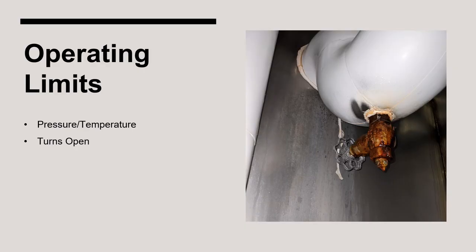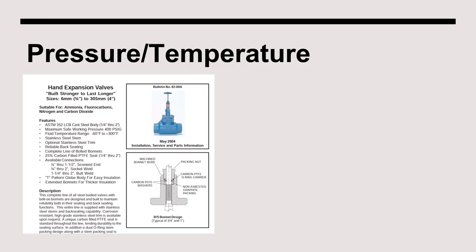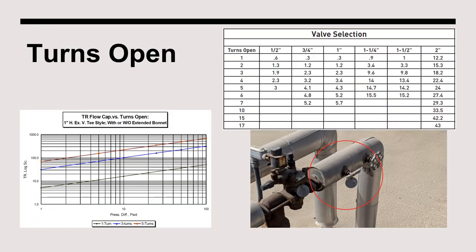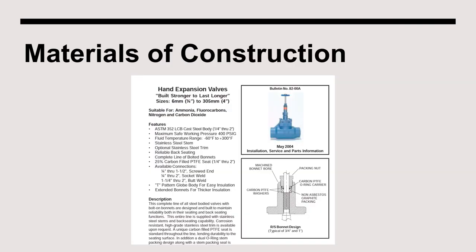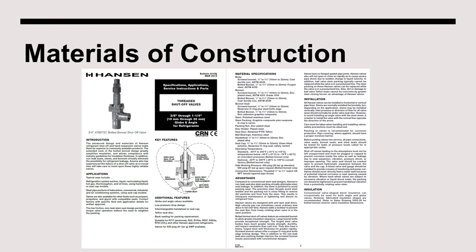We will review the operating limits of valves in terms of rated pressure, temperatures, and turns open of hand expansion valves. The maximum working pressure and operating temperature ranges are provided by the manufacturer in product bulletins and brochures. For example, one valve has a maximum safe working pressure of 400 PSIG. Manufacturers also provide charts and graphs describing flow rate in terms of tons of refrigeration versus number of turns open. The same bulletins and brochures also communicate the materials used to manufacture the valves.